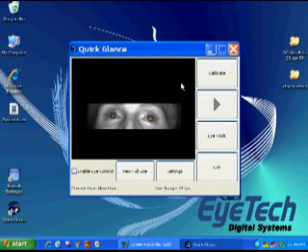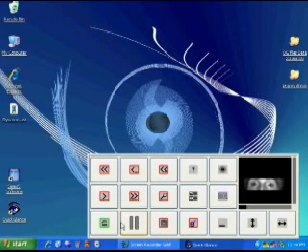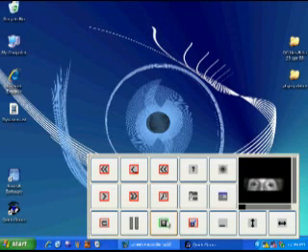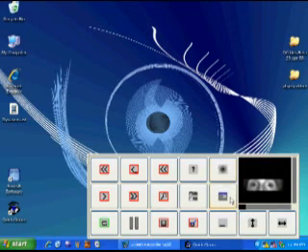As you set up the user, you will first calibrate using a series of a 5-point calibration. There's also an option for a 9 or 16-point calibration. Here you have the eye toolbar that pops up after you're done calibrating, and you have the blink or dwell click options for selecting. You can select the live image of the eye to minimize the toolbar and just show the live image of the eye, or you can minimize the eye toolbar entirely by clicking that button.